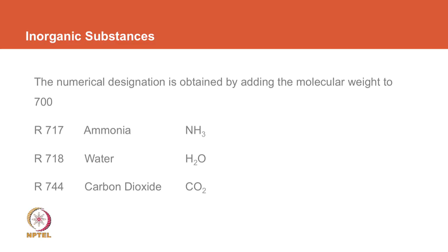We also have inorganic substances, or the ones I was referring to as natural substances, so water, ammonia, carbon dioxide, and here it is simple. You take the number 700 and add the molecular weight to 700, and that is the designation of those. Then we also have mixtures. Nothing limits us from mixing refrigerants together and then trying to see what happens in the system. When we mix refrigerants, we could have two scenarios. In one case, they evaporate at different temperatures and condense at different temperatures, and then we would have a glide. So instead of an evaporating temperature which is 5, we will have evaporation starting at 5 and going up to 7, or starting at 7 and going up to 9, those kinds of scenarios. So we look at a glide between 3 degrees and 7 degrees.